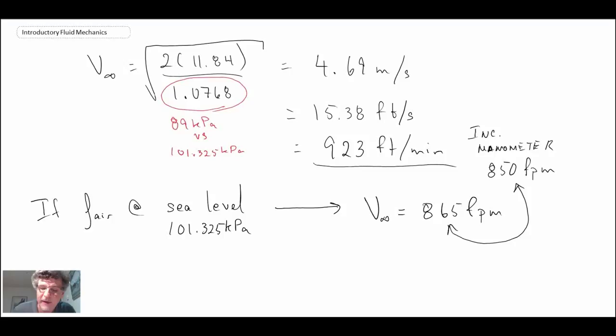For where I did do the experiment, the correct velocities are the ones we have here. So 923 feet per minute or 4.69 meters per second. That gives you an example of making a measurement using the pitot-static tube. I showed you it using an incline manometer, but you can use an electronic pressure transducer or any other type of pressure measurement to figure out what the delta p is on the pitot-static tube.